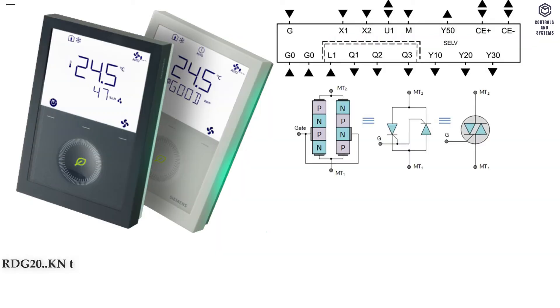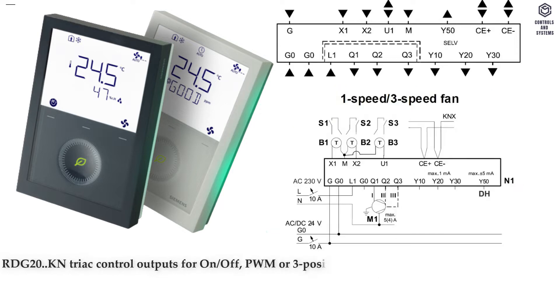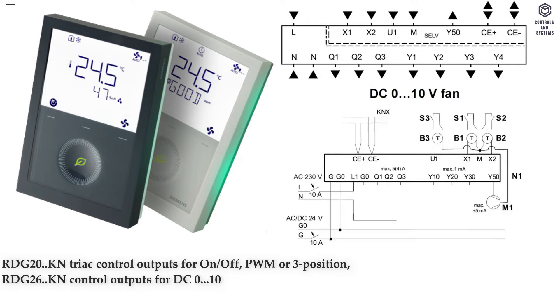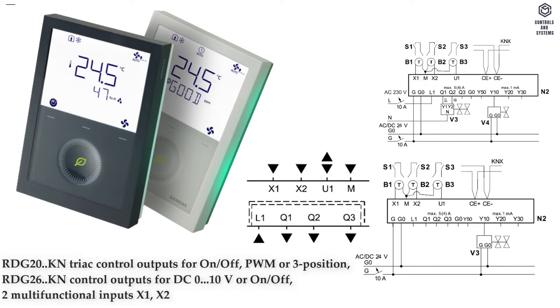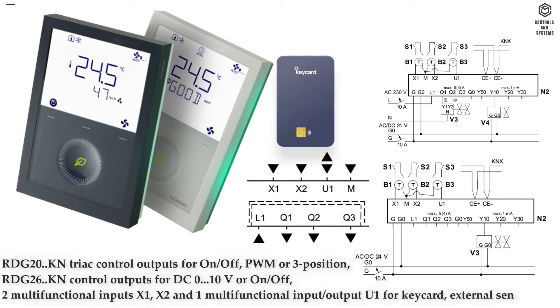The RDG20KN has TRIAC Control Outputs for ON, OFF, PWM, or 3-Position Control. The RDG26KN has Control Outputs for DC 0 to 10 Volt or ON/OFF. There are 2 Multifunctional Inputs X1 and X2, and 1 Multifunctional Input/Output U1 for Keycard, External Sensor, etc.